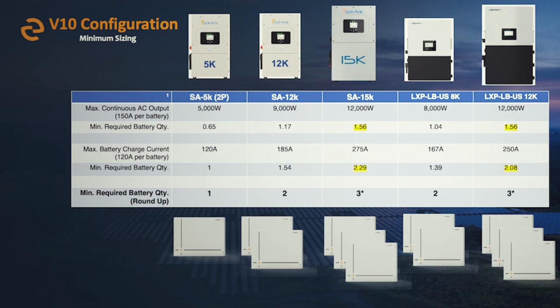I wouldn't say these are required quantities, but maybe more so recommended. Like if you did 3 V10 batteries on a 15K, I think you're good to go. You can use that inverter to its fullest potential without any worry. But I'm not saying that's a requirement, right? So if you're talking to a customer, I personally feel like customers are going to care a lot more about these top numbers than they are about these numbers. Usually that customer is going to place more importance on what can my inverter power, how many kilowatts of output am I getting. They're not really going to care so much about the charge rate. If the system takes an extra hour or 2 to charge up fully, I don't really think too many people are going to be worried about that, but most people, especially for backup applications, want that maximum AC output.